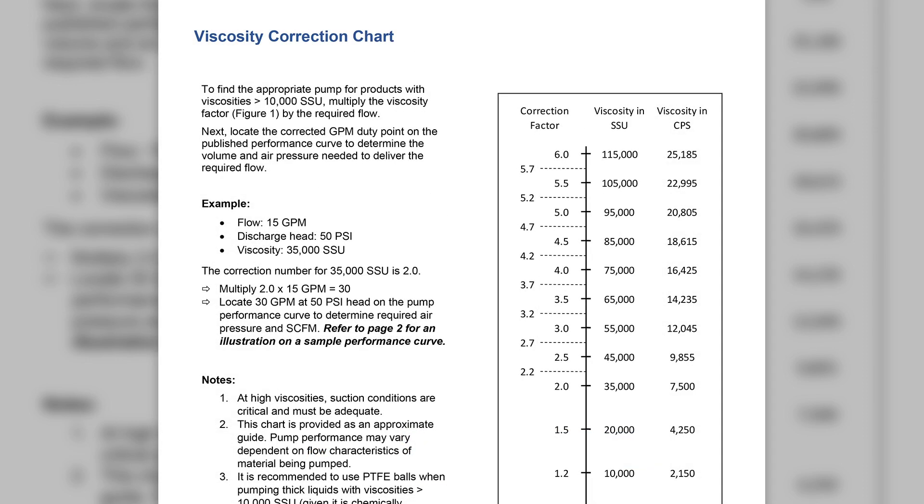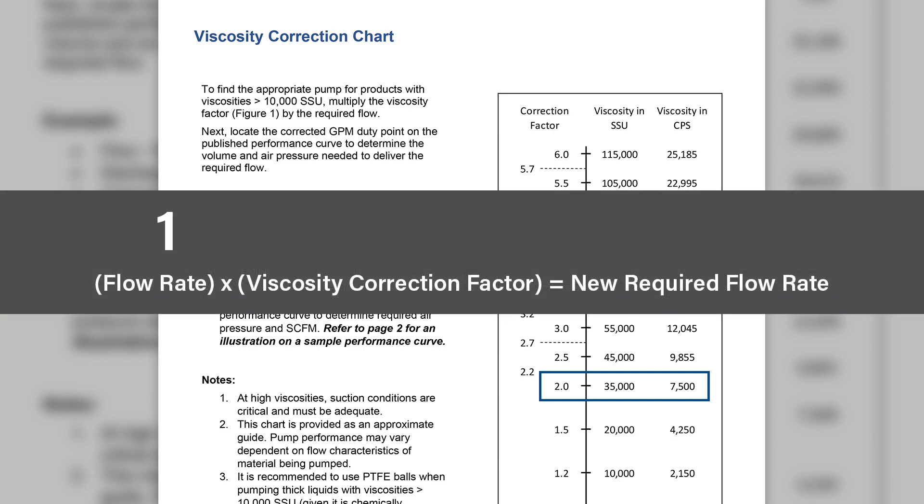In order to obtain the same level of performance as water for the required flow rate of 15 gallons per minute, multiply the flow rate by the viscosity correction factor, in this case, 2.0. The new required flow rate for a viscous product of 7500 centipoise is 30 gallons per minute.